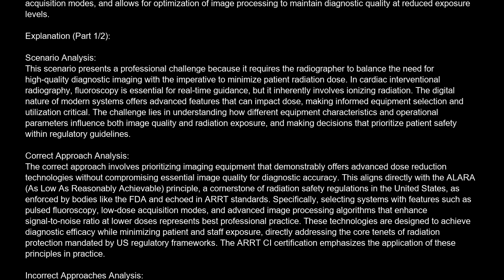Incorrect approaches analysis. One incorrect approach is to solely prioritize the lowest acquisition cost of imaging equipment, disregarding its dose reduction capabilities or image quality potential. This fails to meet the regulatory requirement to implement ALARA, as cost savings should not supersede patient safety and diagnostic efficacy. Another incorrect approach is to select equipment based solely on the highest available frame rate for fluoroscopy, without considering the associated radiation dose implications. While high frame rates can be beneficial for visualizing rapid motion, excessive use without dose optimization can lead to unnecessary radiation exposure, violating ALARA principles and potentially compromising patient outcomes due to cumulative dose.